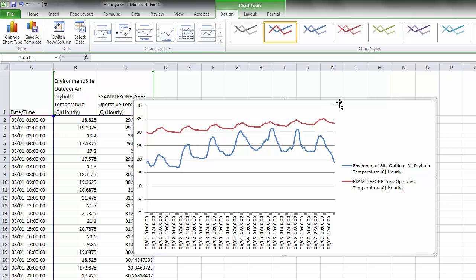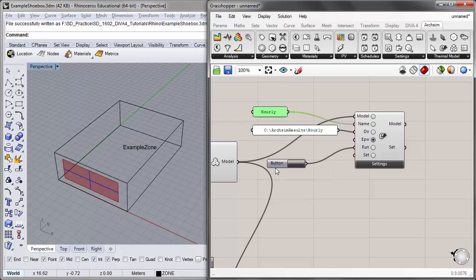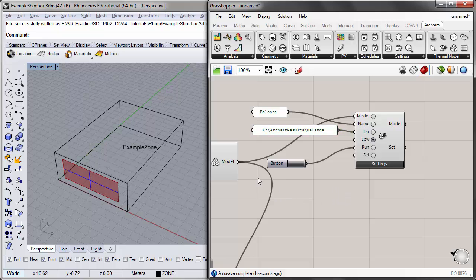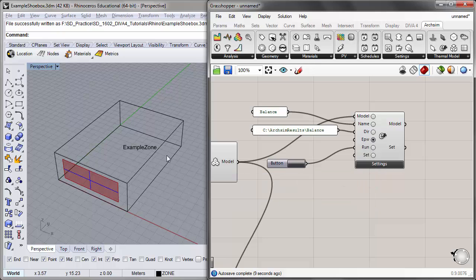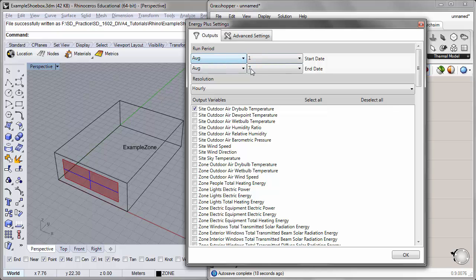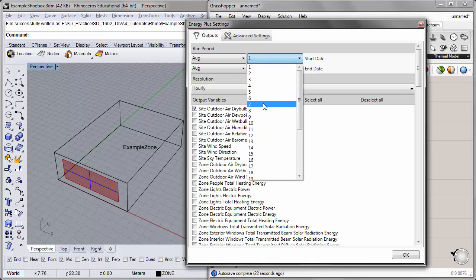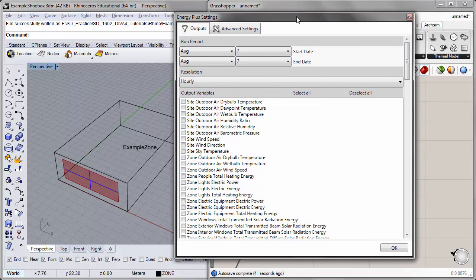Let's take a look at what is causing this overheating by looking at the energy balance for a specific day. I'll change the simulation name to 'balance' and change the directory name to 'balance.' I want to modify the settings in the EnergyPlus component to isolate the specific gains and losses within my space. To make the graph more legible, I can limit this to just the last day of the simulation — August 7th. I'll deselect the temperature output variables. Rather, I want to look at the components of the heat gains and losses to understand what's contributing to that overheating.